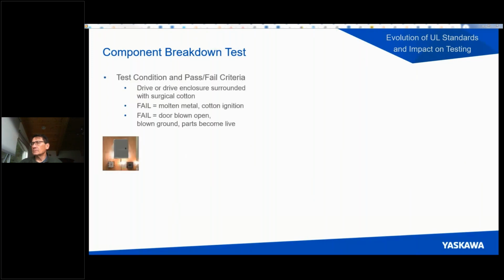So let's discuss the component breakdown test just a little more. The test condition is such that we must surround the equipment under test with surgical cotton. When we're trying to determine the conditions for a drive by itself to pass the test, the cotton directly surrounds just the drive. But when we're trying to determine how the drive will pass when installed in a cabinet, the cotton surrounds the cabinet rather than the drive inside the cabinet. As we discussed on a previous slide, the purposely created internal short circuit is usually destructive. But destroying the drive does not mean it's a failed test. A test is considered a fail when the surrounding cotton ignites, when there is molten metal on the exterior, when a door or cover is blown off, when a ground connection is blown, or when a touch surface becomes live.